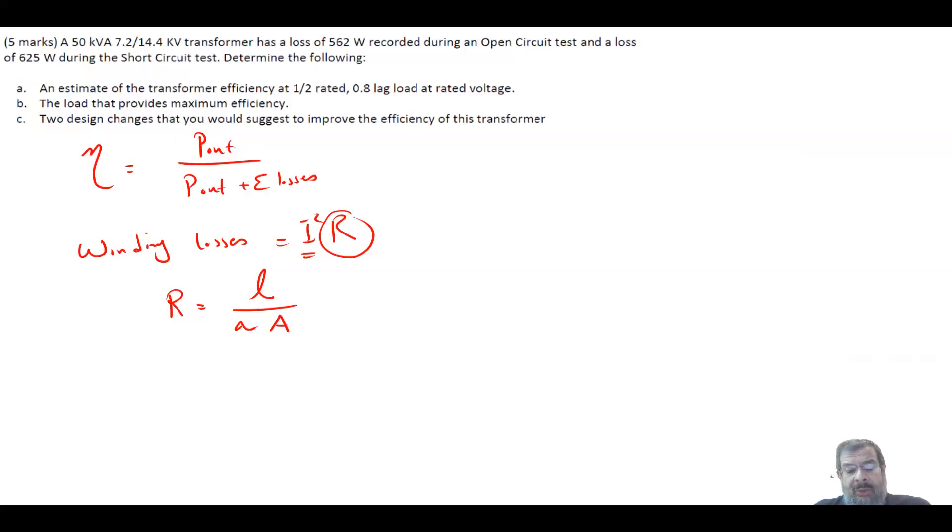And this R is equal to L over conductivity times A. So one way to change is the conductivity by using a material. We have either copper or aluminum. Obviously, copper has a better conductivity. So if you are using aluminum, use copper. This will reduce the R. Or, and this is more common, because most people use one material, either aluminum or copper, change the A. What is A? It's the cross-sectional area. So the conductor cross-sectional area A, increase this. So once you increase A, then R will be reduced. Then your winding loss will be reduced as well.